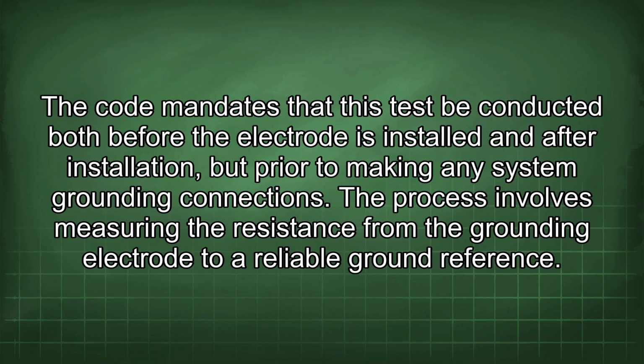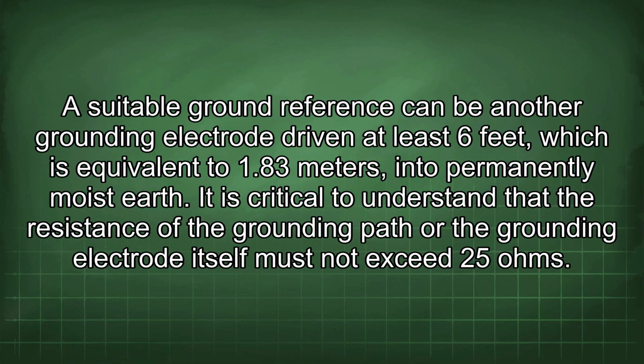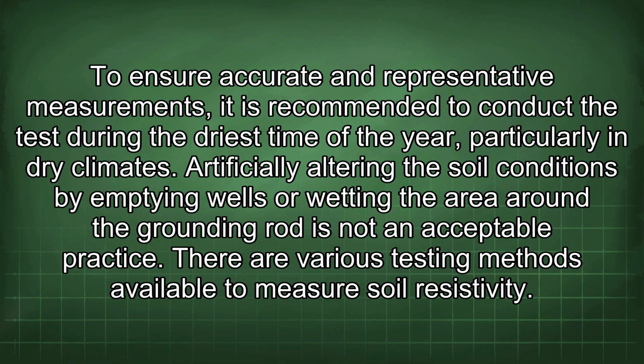The process involves measuring the resistance from the grounding electrode to a reliable ground reference. A suitable ground reference can be another grounding electrode driven at least 6 feet, which is equivalent to 1.83 meters, into permanently moist earth. It is critical to understand that the resistance of the grounding path or the grounding electrode itself must not exceed 25 ohms. To ensure accurate and representative measurements, it is recommended to conduct the test during the driest time of the year, particularly in dry climates. Artificially altering the soil conditions by emptying wells or wetting the area around the grounding rod is not an acceptable practice.